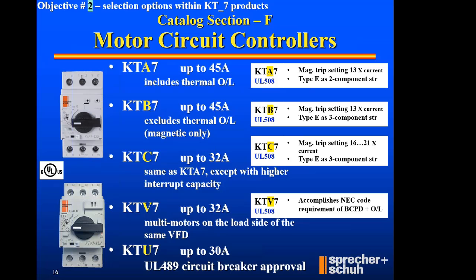Moving on to a KTC7, which is basically the same thing as a KTA7. Whoop, I got a typo on the screen, and that it's a 2-component starter. And it's just like a KTA7, except now I've got a higher inrush current. So let's say I'm using a KTA7, but I'm using it on a function that has a higher inrush, or it takes a longer period of time to come up to full speed or whatever. The higher inrush would be a circumstance of selecting a KTC7. So the higher of a 16 to 21 times the inrush current. So that would be a resolution for higher inrush, or things that take longer time to come up.